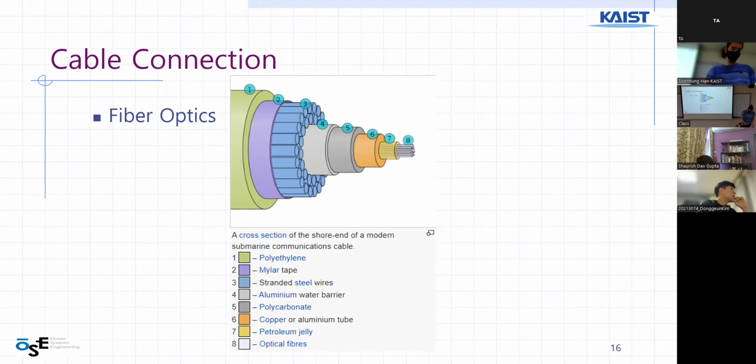And to conclude, we concluded that we will use a cable connection and that tidal power generation is able to generate enough electricity compared to the power consumption of an average data center. The traditional data center uses much power to operate and sustain the center itself. The average PUE of a large data center was around 1.57, but the underwater data center has a PUE of 1.07, which is much more effective.